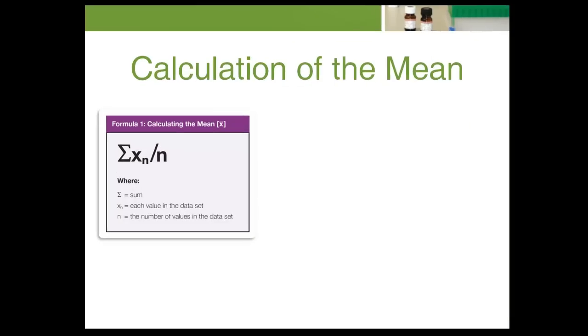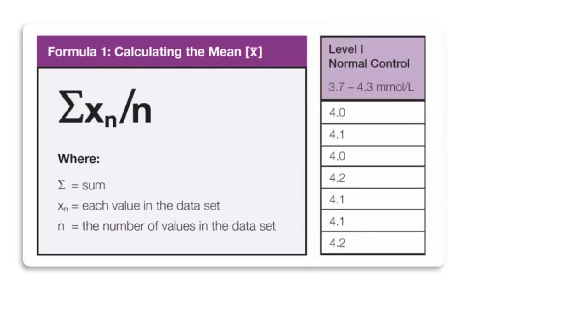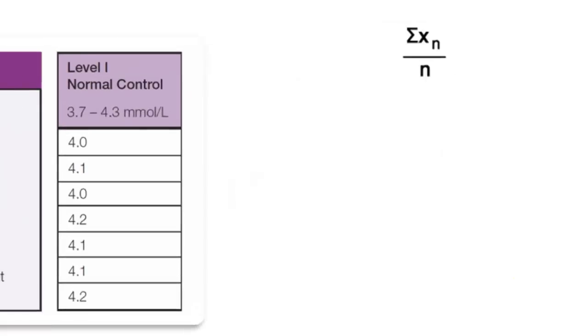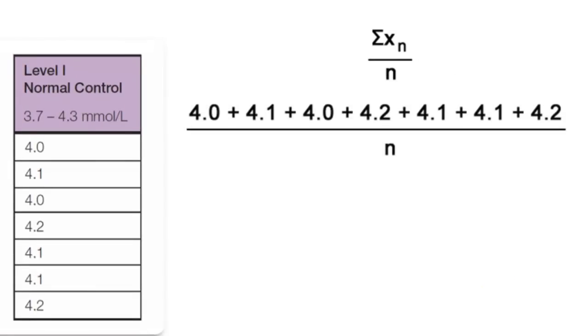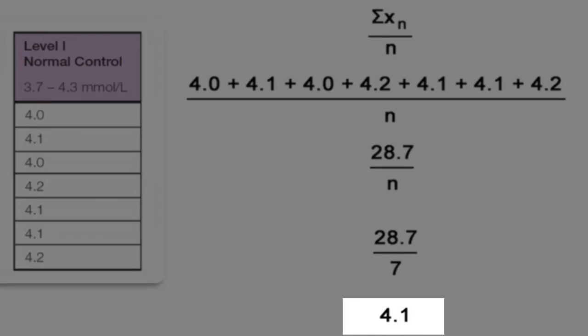To calculate a mean for a specific level of control, first add all the values collected for that control, then divide the sum of these values by the total number of values. For instance, to calculate the mean for the normal control, level 1, find the sum of the data. The sum is 28.7 millimole per liter, and the number of values is 7. Therefore, the mean for the normal control is 4.1 millimole per liter.